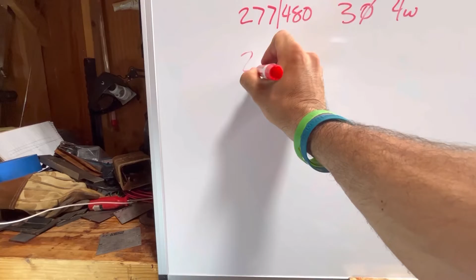Let's say it's a 240/480, three-phase, four-wire. 240 divides evenly into 480. Therefore, this connection would be a delta connection. 277/480. That does not divide evenly into each other. Therefore, it's going to be a Y connection. 120/240, three-phase, four-wire. Obviously divides evenly. It's going to be a delta connection.